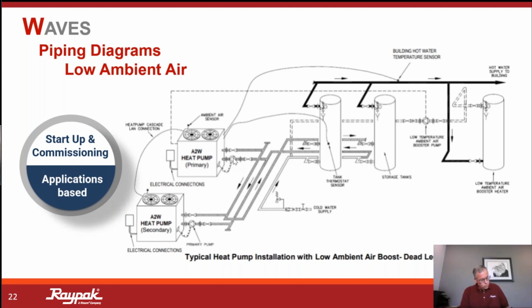And we recommend that the low ambient backup is set for 140 degrees. So the auxiliary booster or the low ambient backup will remain active until the water heater fault is cleared, or until it reaches that set point.